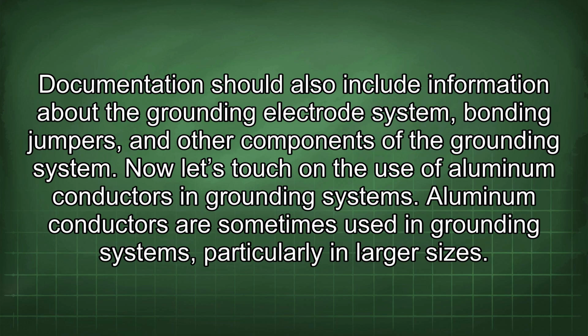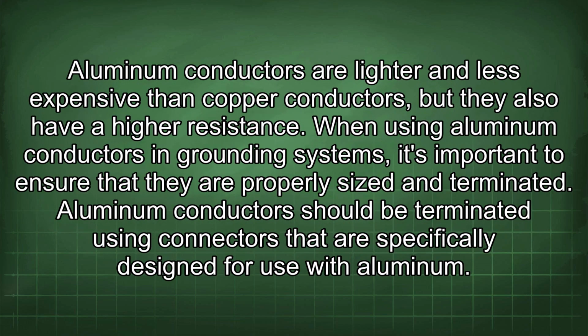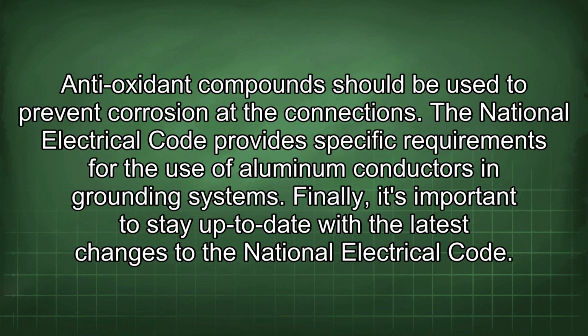Now let's touch on the use of aluminum conductors in grounding systems. Aluminum conductors are sometimes used in grounding systems, particularly in larger sizes. Aluminum conductors are lighter and less expensive than copper conductors, but they also have a higher resistance. When using aluminum conductors in grounding systems, it's important to ensure that they are properly sized and terminated. Aluminum conductors should be terminated using connectors that are specifically designed for use with aluminum. Antioxidant compounds should be used to prevent corrosion at the connections. The National Electrical Code provides specific requirements for the use of aluminum conductors in grounding systems.